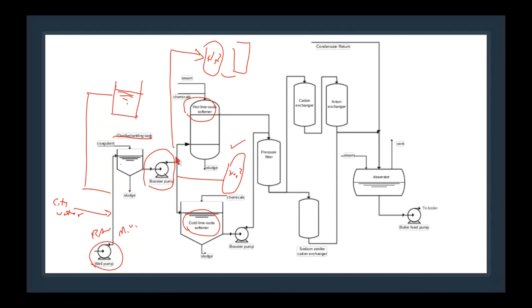So that softened water goes to boiler number 1 and boiler number 2, and I think it goes also up to the 4th floor for the low pressure steam boilers and the high pressure Cleaver Brooks. But then as for Unit number 4, we've got a system that's very, very intolerant of dissolved solids.